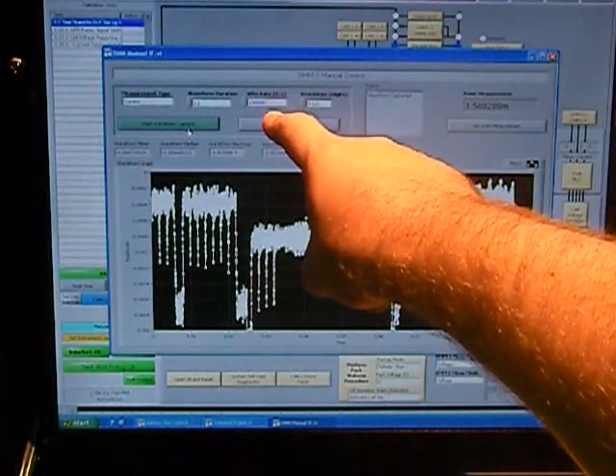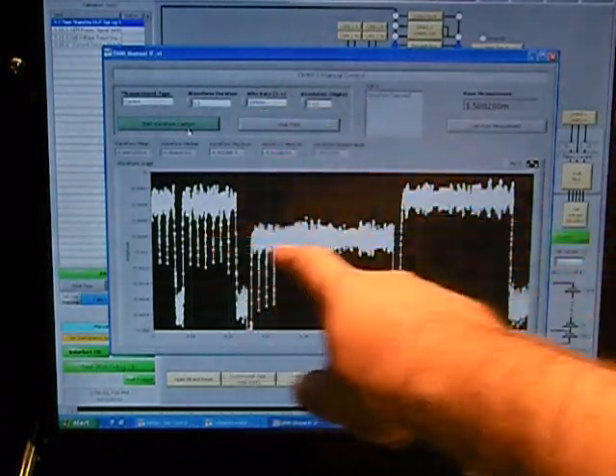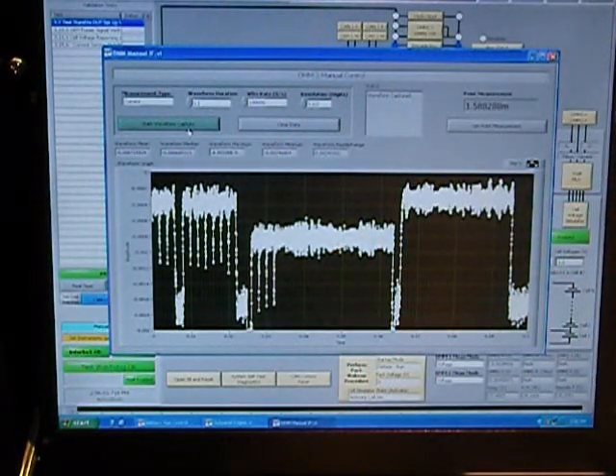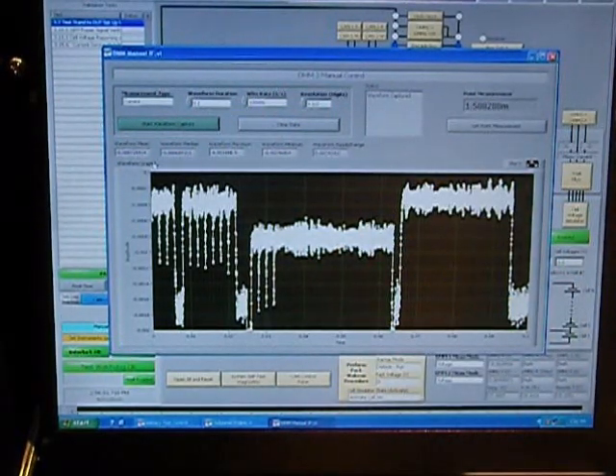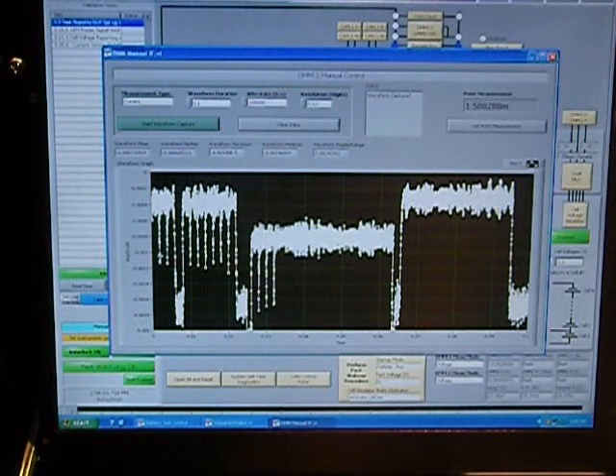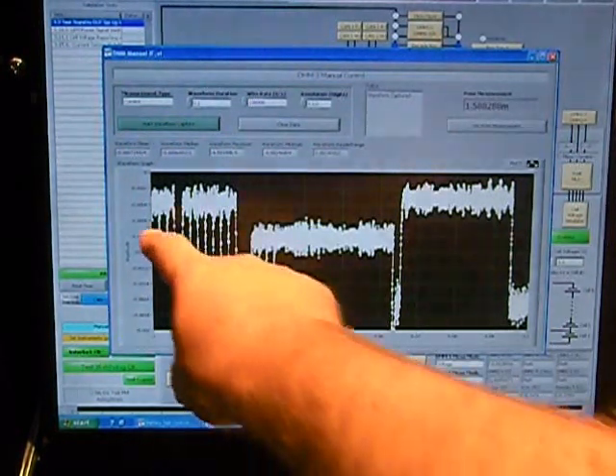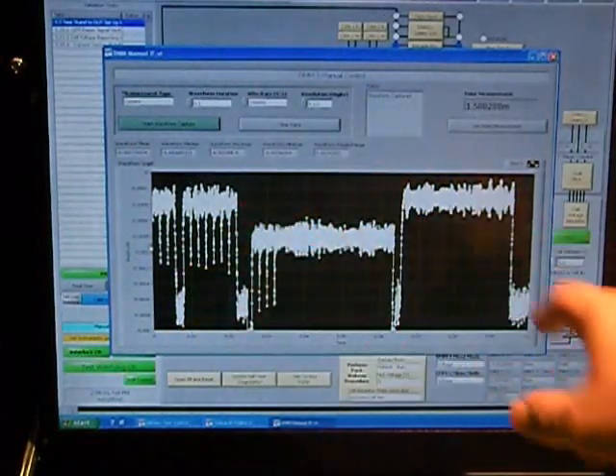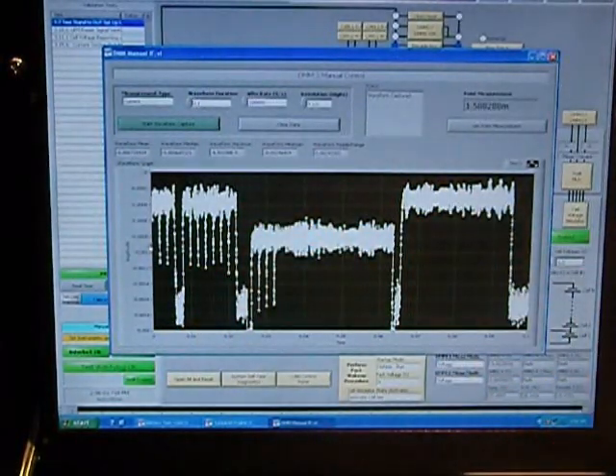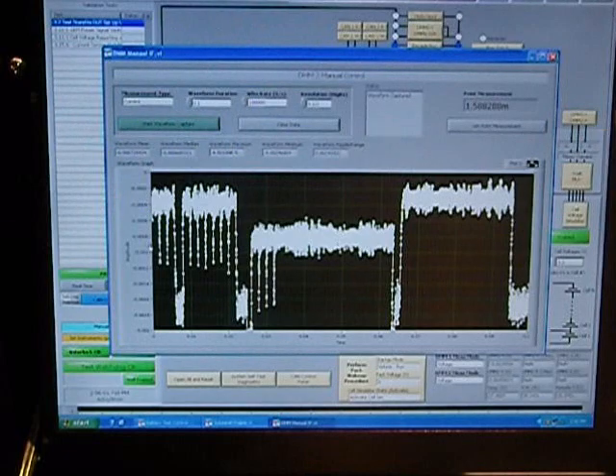And you can see this is the amount of current flowing on that supply line. We've set the waveform duration for a tenth of a second. The sample rate to 100,000 samples per second. This is actually 10,000 measurement points with five and a half digits of resolution. You can see that the mean value is about 7 milliamps right here.